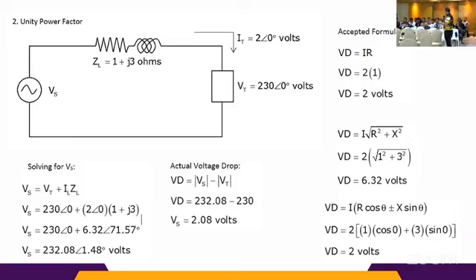So for unity power factor, the value of the voltage drop is different. The voltage drop is 2.08 volts. So that is the voltage drop. So instead of VS, the voltage drop should be 2.08 volts. So there's another way of solving, using the resistance, the impedance, and using the triangle. So we come up with the voltage drop, that is 2 volts. Okay? Alam niyo yet dito, no?